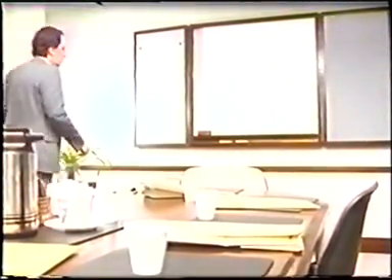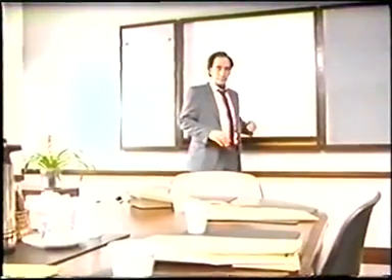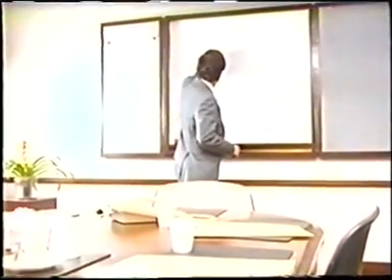Sometimes the alarm will sound only on the fire floor and the 2 floors above and below it. It's just not necessary for the entire building to respond to the initial alarm. It's very likely that the fire will be quickly extinguished at its source, in which case there's no real need to evacuate beyond the immediate area of the fire. Any alarm means take action. People on the affected floors respond according to their plan, as they've practiced in drills.